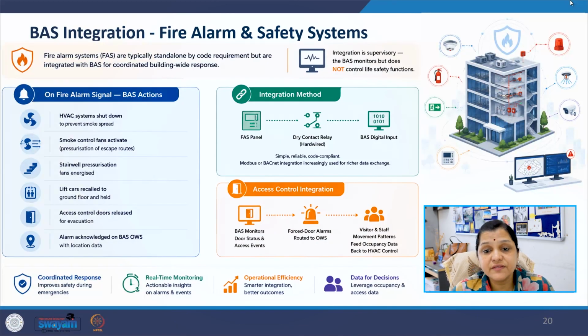Next is building automation integration with fire alarms and safety systems. Fire alarms are generally standalone for safety and code compliance reasons, but BAS integration enables a coordinated response. During a fire event, HVAC systems shut down to limit smoke spread. Stair pressurization fans activate, lifts return to ground level, and the access control system releases doors for evacuation. The building automation system monitors these events and displays alarm information on operator workstations. Integration may occur through hardwired relay connections or through communication protocols such as BACnet and Modbus. Access control integration allows occupancy related information to support HVAC optimization also.